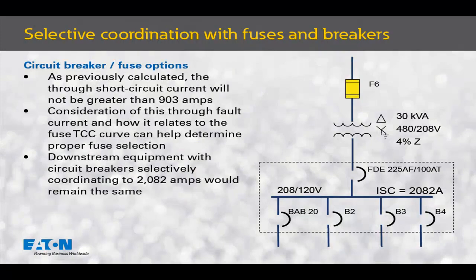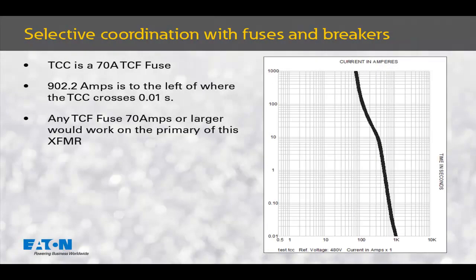Knowing that the primary fuse will see 903 amps during this short circuit event on the secondary, we review the time current characteristic curve for the fuse to determine selectivity with the circuit breakers on the secondary. To achieve selectivity, the TCC must show that the through short circuit current of 903 amps is less than where the fuse curve crosses 0.01 seconds. This is the trip curve for the TCF 70 amp fuse. The 903 amps of primary short circuit current is to the left of where the fuse curve crosses 0.01 seconds, telling us that any TCF fuse 70 amps and greater will work on the primary of this transformer.